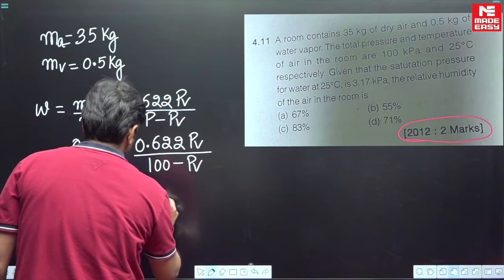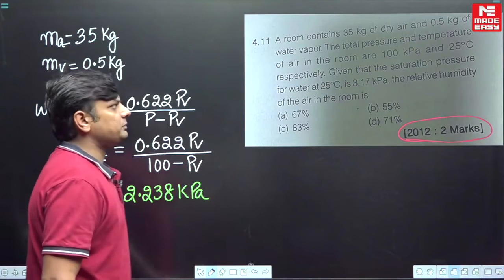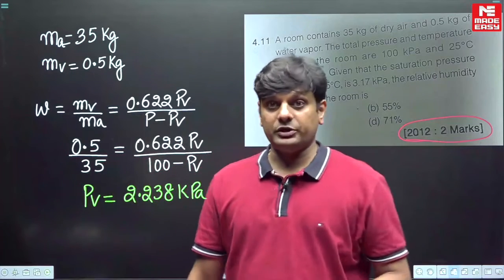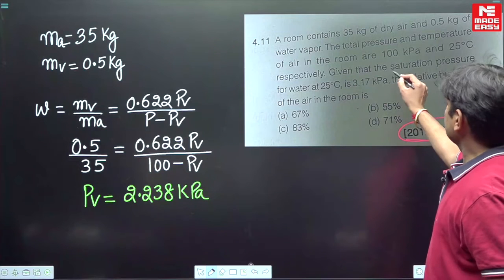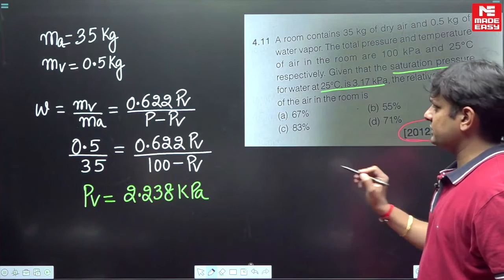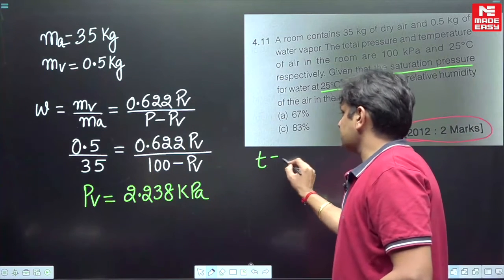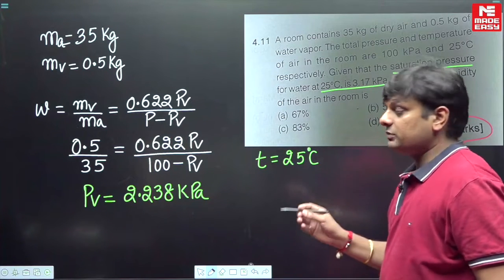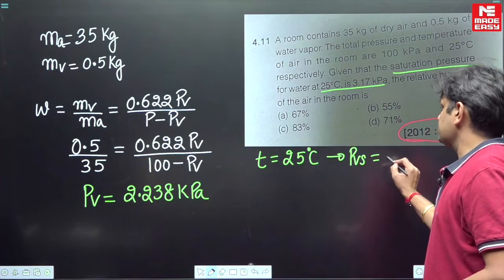Solving this equation, you will get the value of pv = 2.238 kPa. Here pv is the partial pressure of water vapor. Now read the question carefully: the saturation pressure of water at 25°C is given as 3.17 kPa. The 25°C is the dry bulb temperature — the temperature of moist air measured by a simple ordinary thermometer.